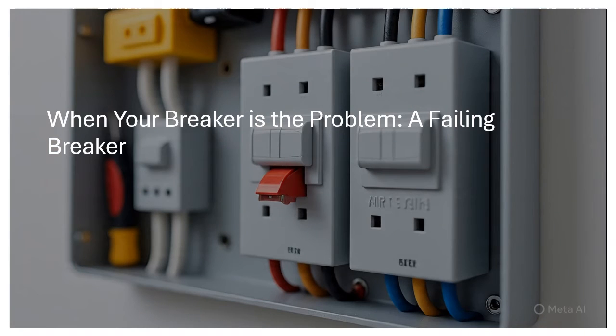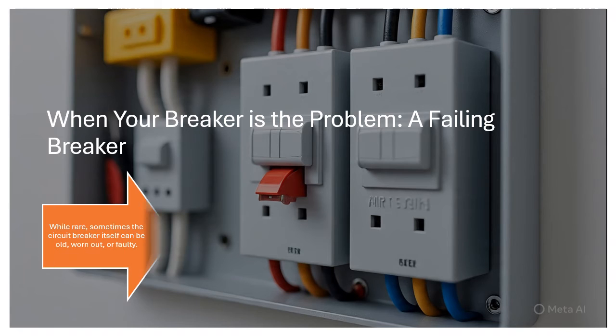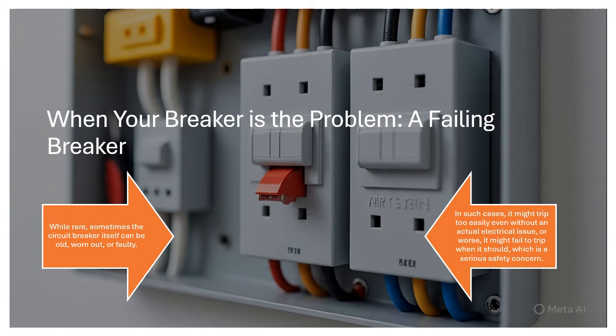When your breaker is the problem, a failing breaker. While rare, sometimes the circuit breaker itself can be old, worn out, or faulty. In such cases, it might trip too easily even without an actual electrical issue, or worse, it might fail to trip when it should, which is a serious safety concern.